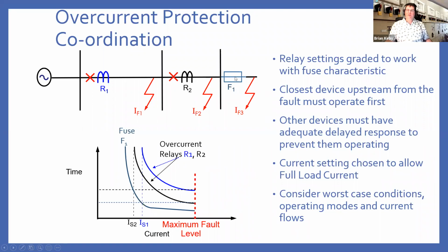So what we do is the fuse has a fixed characteristic, and we will get that from the manufacturer, and it looks something like this. So we will have a maximum fault level and an operating time for the fuse. So as the current increases, the time for the fuse to operate decreases. What we then do is our relays 1 and 2, we will use a protection characteristic that emulates a fuse characteristic. So here, relay 1, the blue line, relay 2.